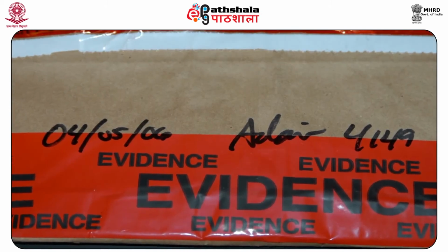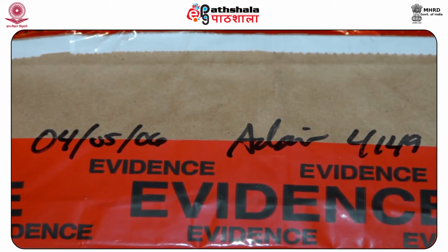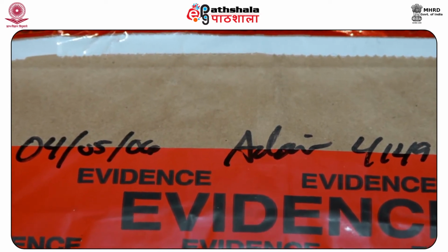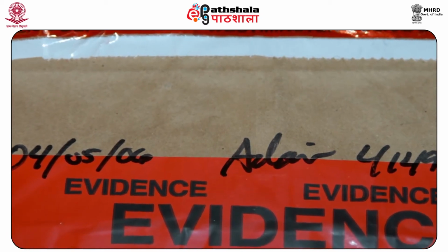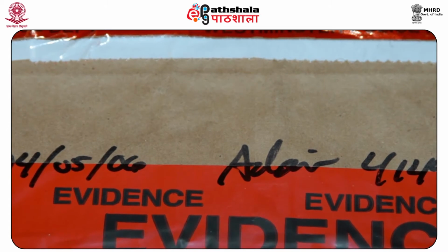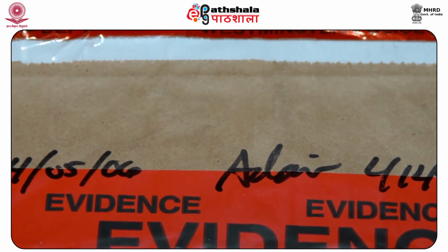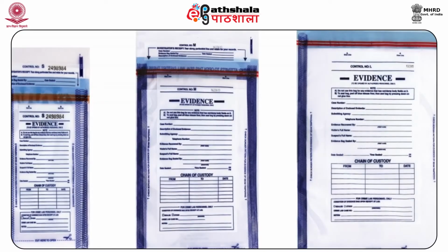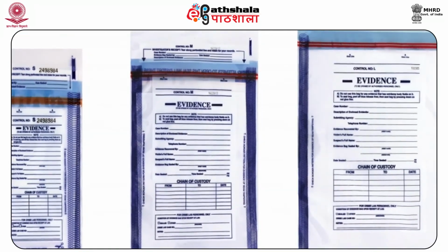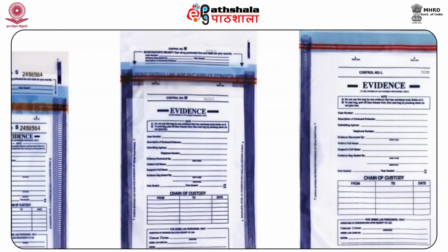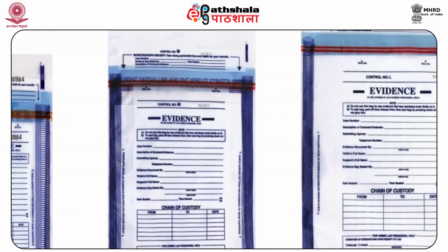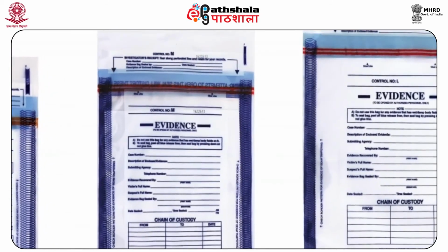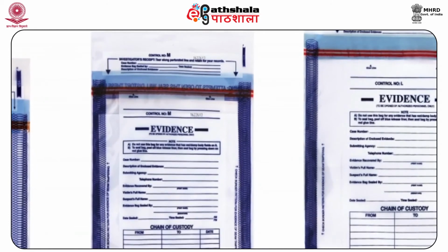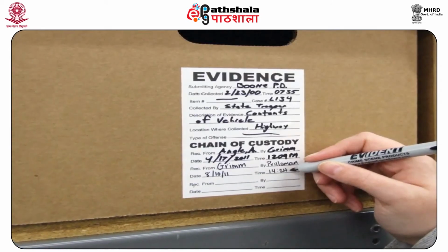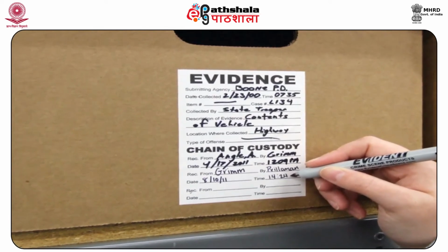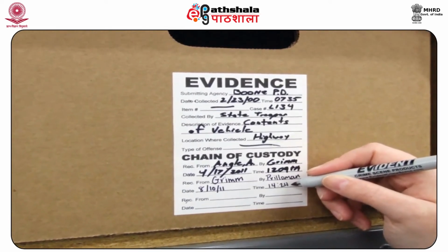Each individual item of evidence must be marked with a unique case number designator for identification. Should the item not lend itself to marking, its proximal container must be marked. Labeling on caps or lids alone is not acceptable because of the risk of wrongly replacing the lids during batch testing of similar samples. The identification should be retained throughout the life of the item in the laboratory.